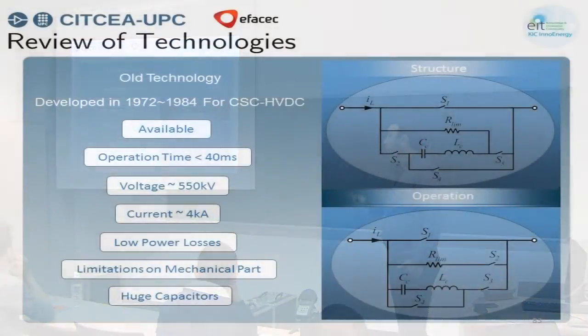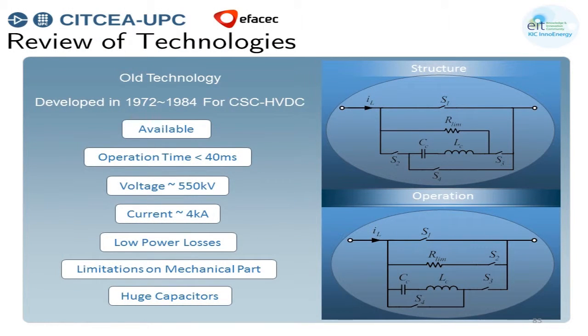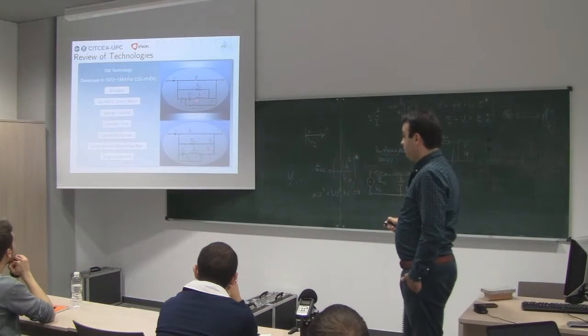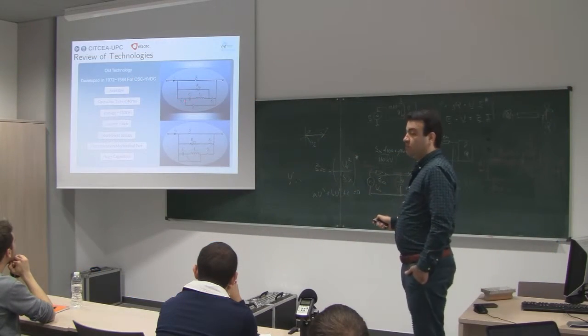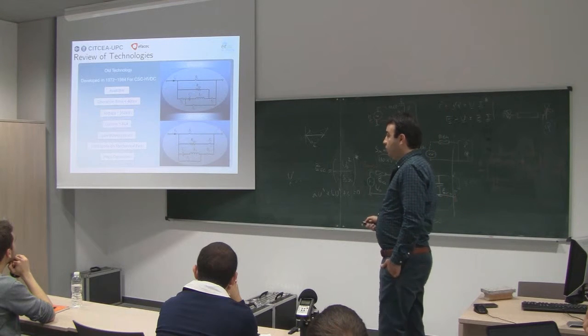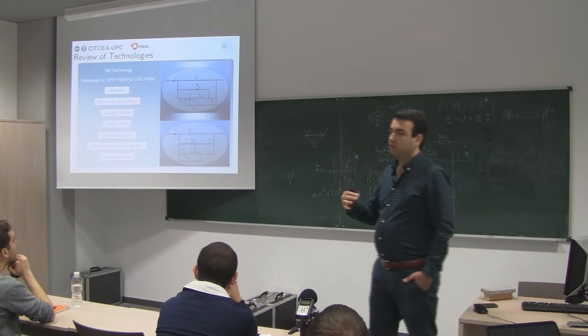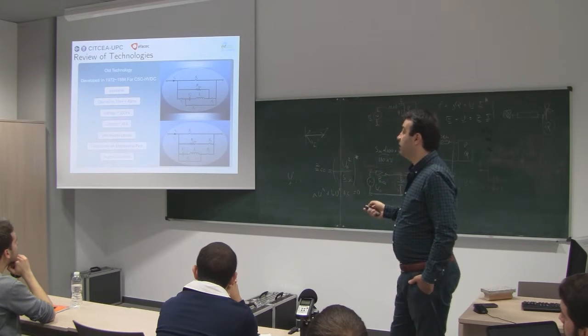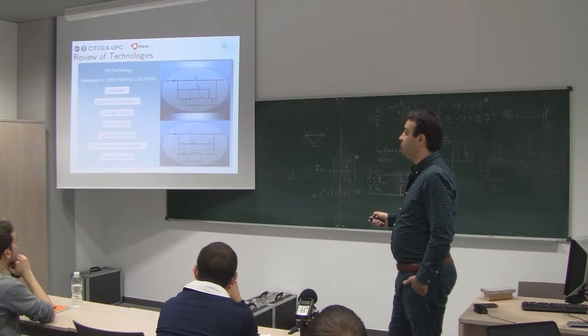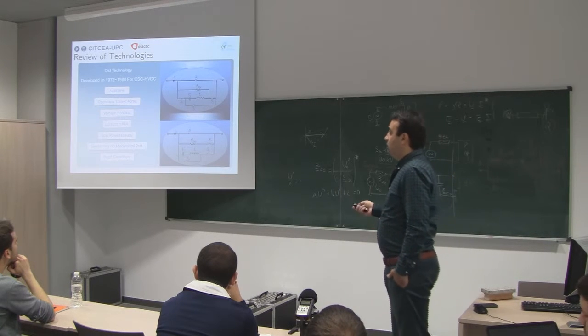Then we have another technology, which is again from almost the same time, 1972 till 1984, and it is the active mechanical HVDC circuit breaker. And here you have some other kind of topologies which are attached to these mechanical breakers. And usually you have this capacitor charged with this circuit, and then you will be able to quench the current in the mechanical breaker in less time, which I would say is less than 40 milliseconds. And the other things are almost the same.